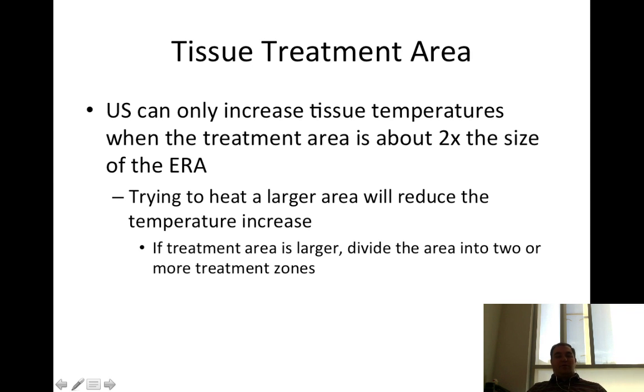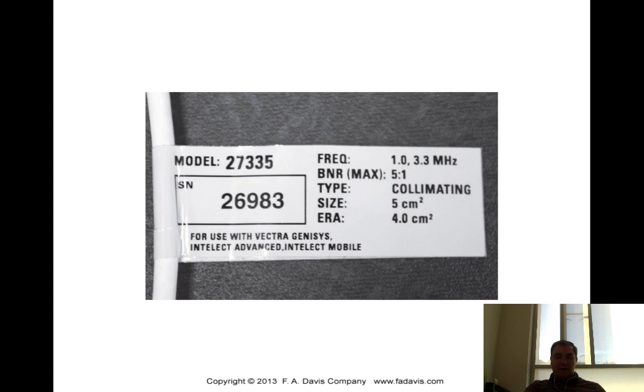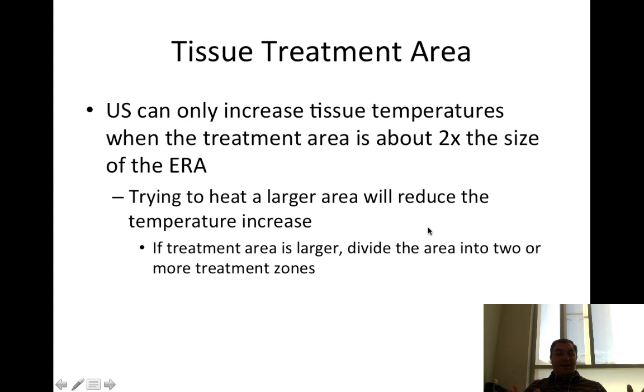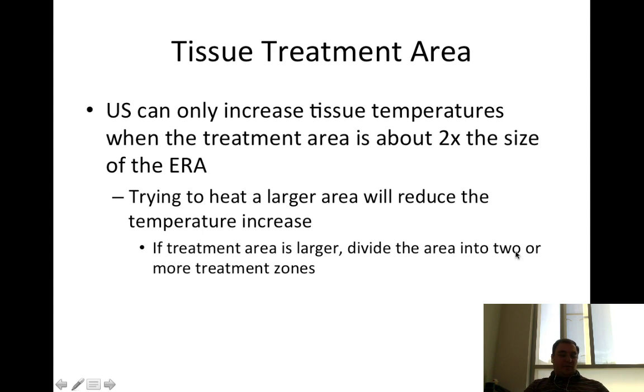Ultrasound can only increase tissue temperatures when the treatment area is about two times the size of the ERA — the effective radiating area. So if the ERA is 4 centimeters squared, you can only cover about 8 centimeters squared, two times the ERA. Trying to heat a larger area would reduce the temperature increase. If the treatment area is larger, divide it into two or more treatment zones.